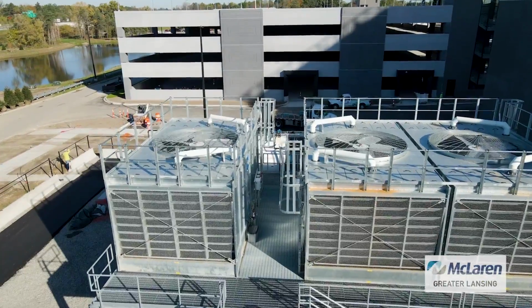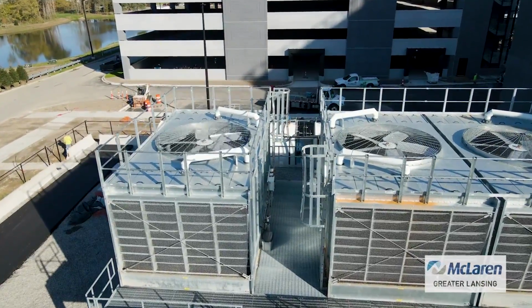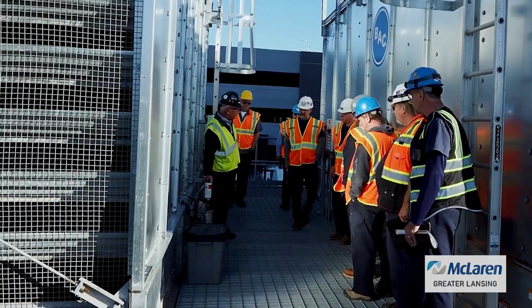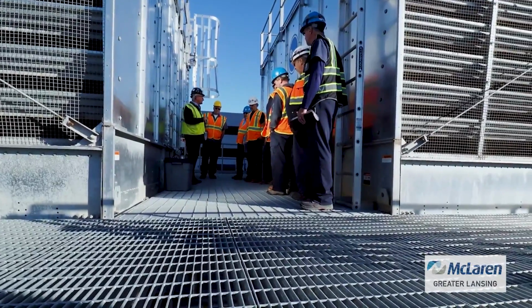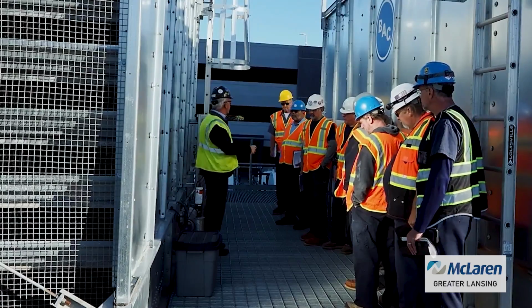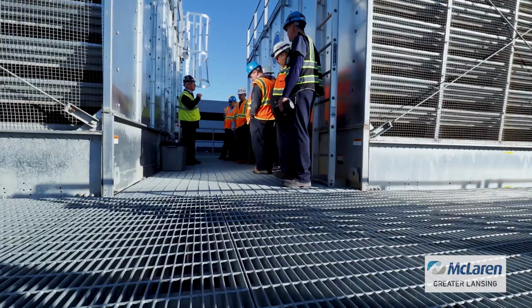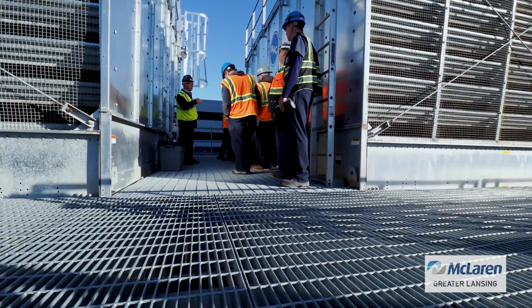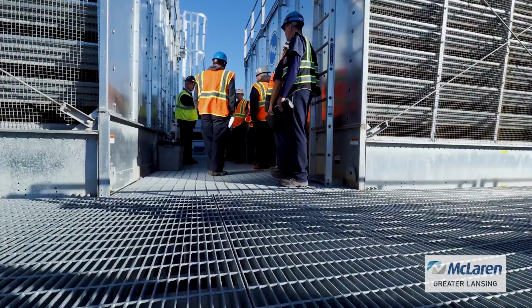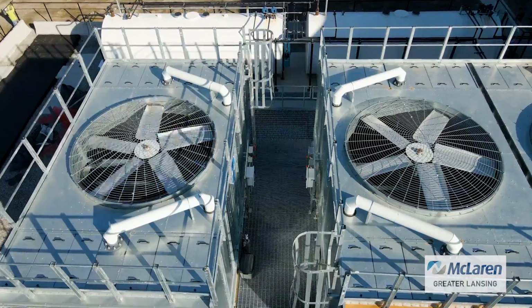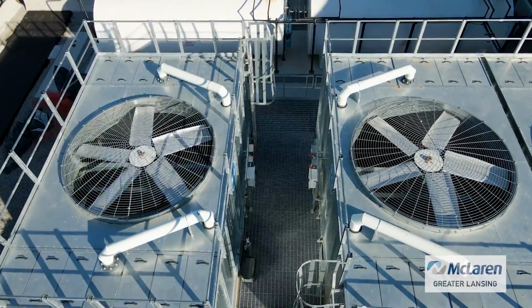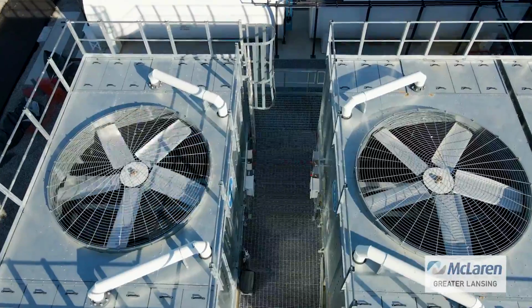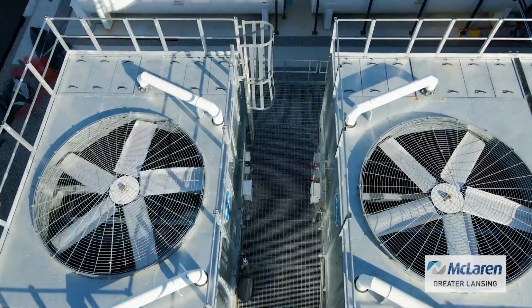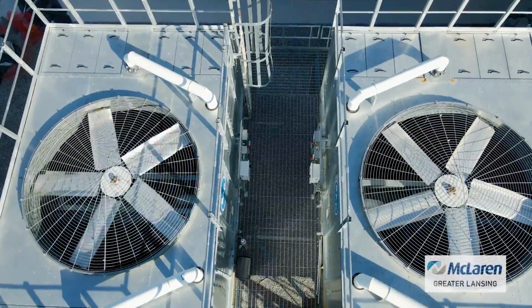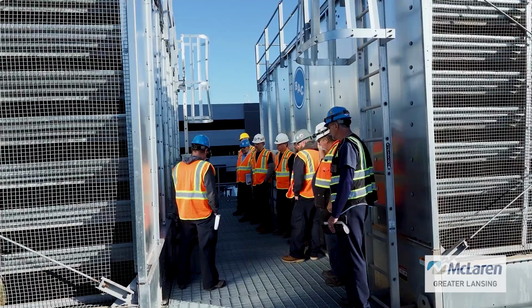It's a novel way to do this on multi-cell cooling towers. So level control's right here, and it's measuring the water. So back up the horse. Multiple cell cooling towers that share a common suction header have to be what's called equalized. So the water levels are all the same all the time through the equalizer line. This is tied into the equalizer line. So periodically you're going to need to pull that and clean it.